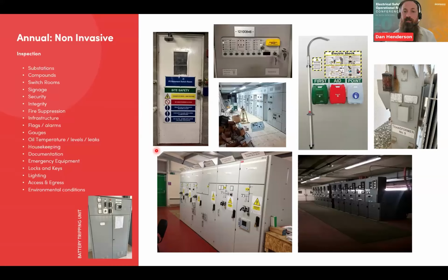And I've seen so many times where operators will leave the panel enabled and just go inside. When you ask them what's the logic behind this, they'll say, well, it gives you an alarm of 30 seconds if there's a fire detected, so you've got loads of time to get out. But I wouldn't be racing against 20-something bottles of CO2 being discharged into the space, which removes the oxygen. You could fall over, you could trip, you could be disorientated.